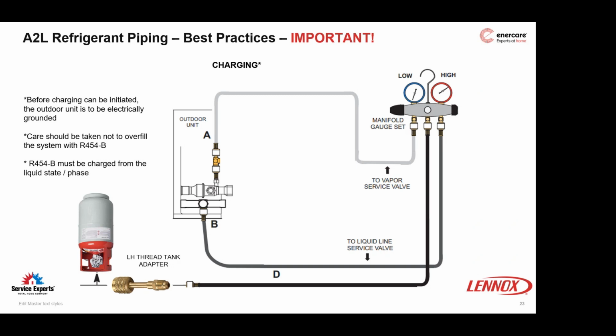And then, like I said, anything else? A couple of key points. Just like 410A, R454B is a blend, and it has to be charged as a liquid. The only reason it's pictured upside down here is that it cannot be charged as a vapor. You get fractionation and basically lose the effectiveness of the refrigerant.